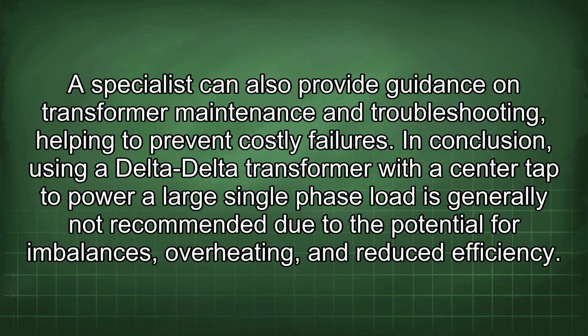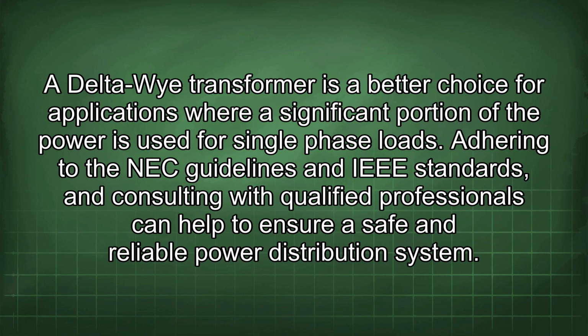In conclusion, using a delta-delta transformer with a center tap to power a large single-phase load is generally not recommended due to the potential for imbalances, overheating, and reduced efficiency. A Delta-Wye transformer is a better choice for applications where a significant portion of the power is used for single-phase loads. Adhering to the NEC guidelines and IEEE standards and consulting with qualified professionals can help to ensure a safe and reliable power distribution system.